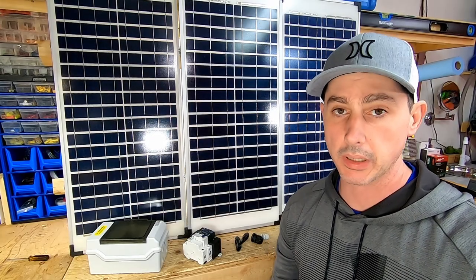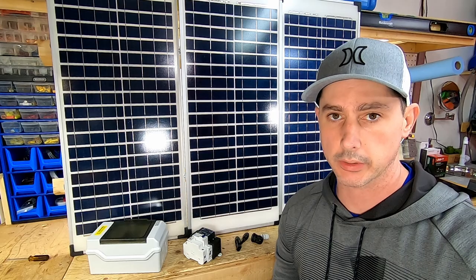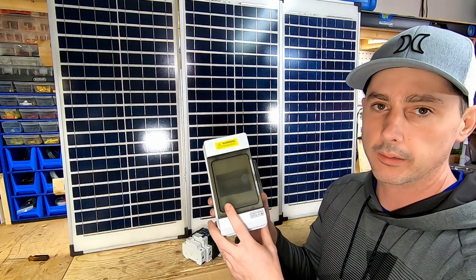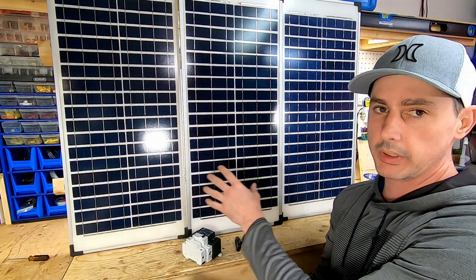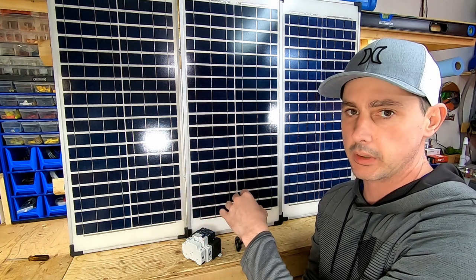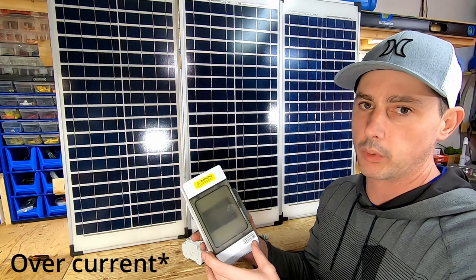In this video I'm going to be making a main disconnect, over voltage protection, and surge protection all in a convenient little box enclosure. I'm going to be mounting three solar panels, 40 watts each, and running them in series. So this isn't a combiner box — it's more or less an over voltage protection and disconnect.